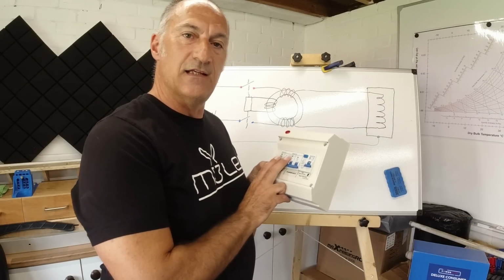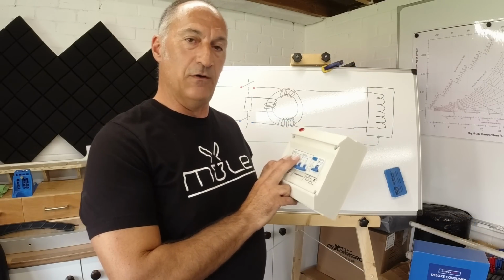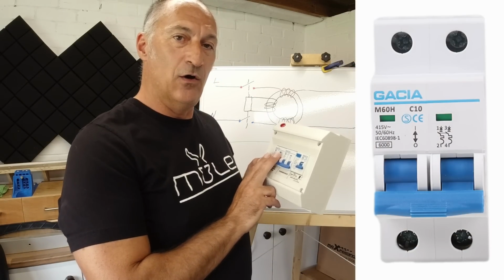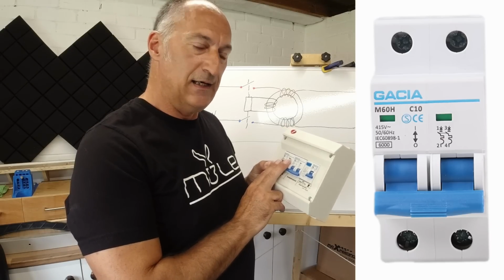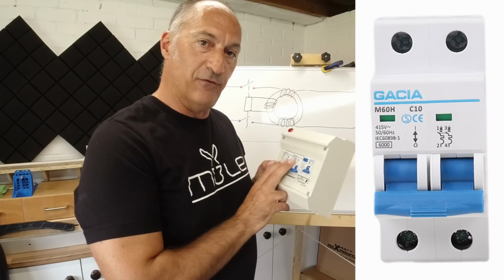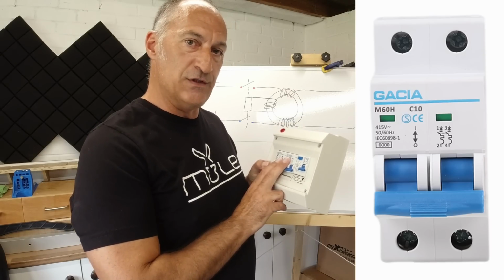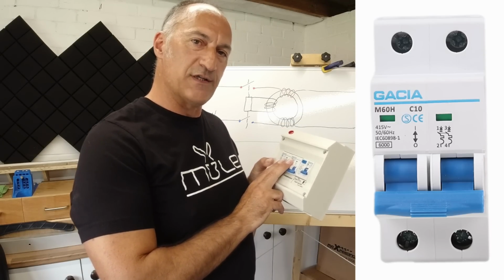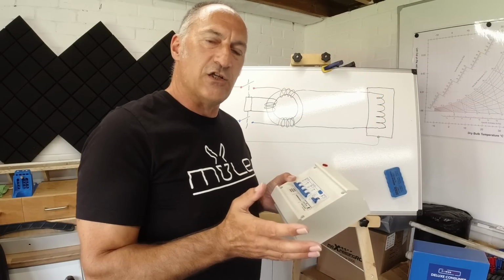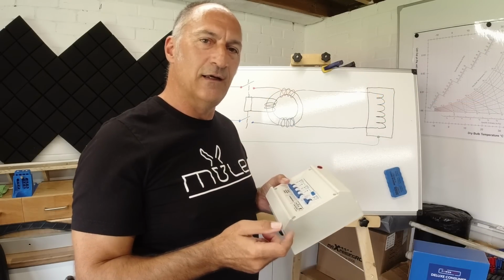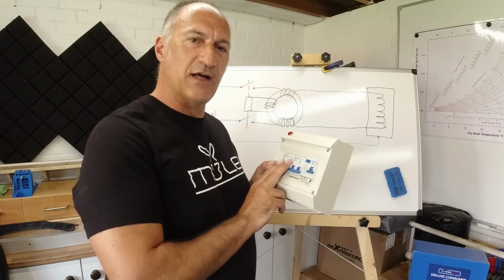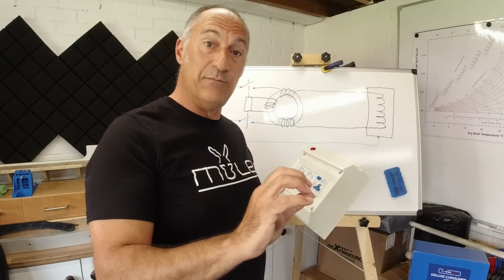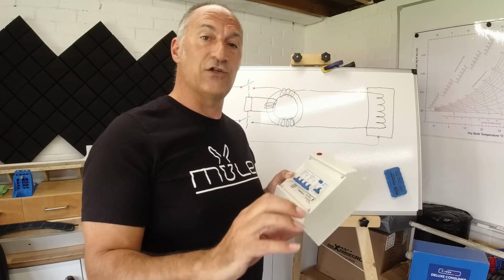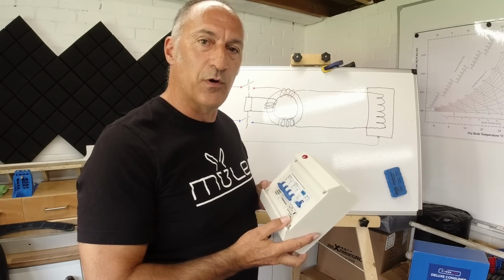So that is where the second device comes in the consumer unit, and they are the MCBs, or miniature circuit breakers. And as we touched on briefly before, basically they are like a fuse. So they're there for overcurrent protection. In an overcurrent situation where you've got high current flowing, you want this device to break the circuit before those cables get too hot and could catch fire, obviously causing you a major problem.